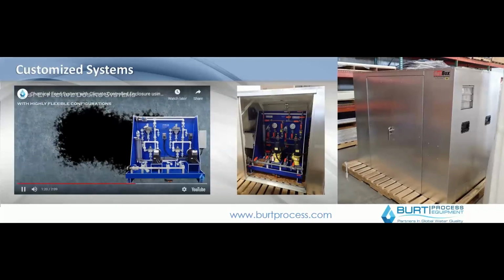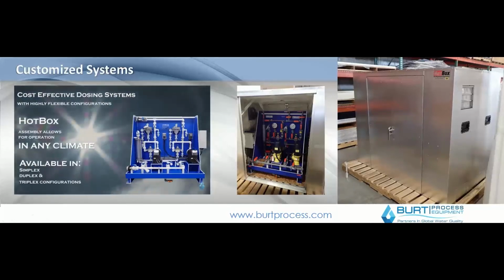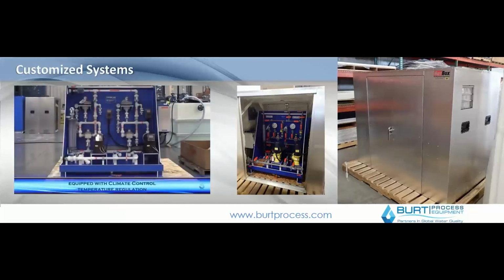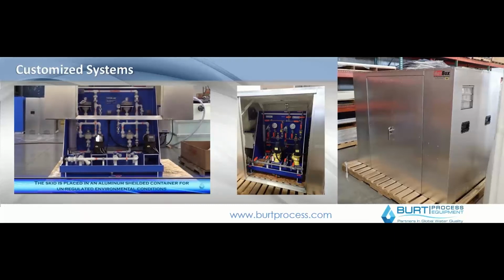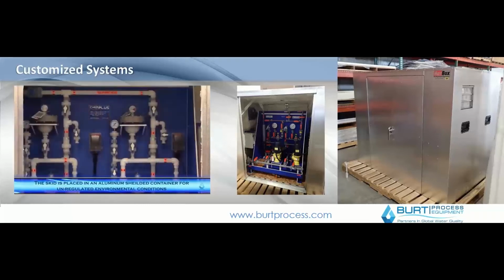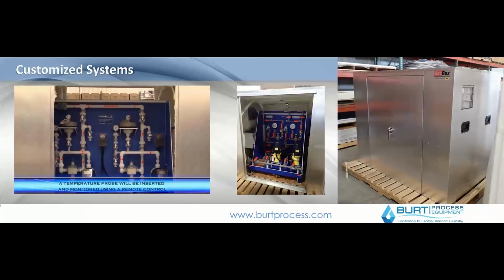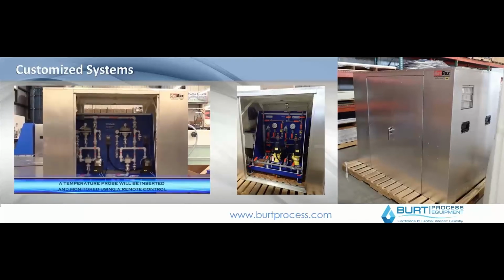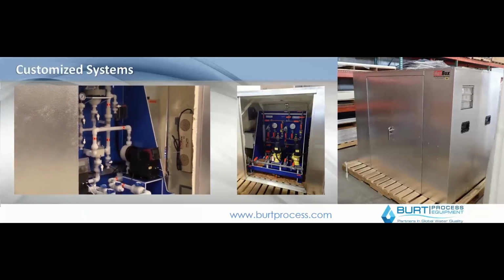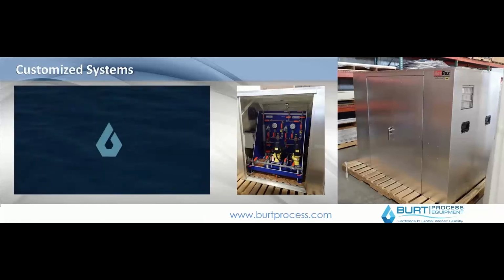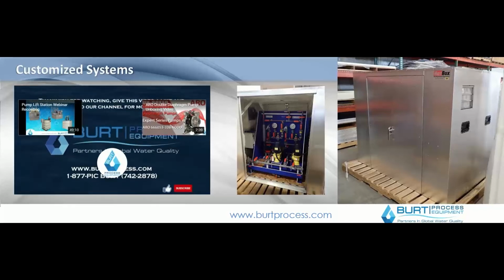Controls can vary quite a bit with these different types of systems, whether it's going to be a full PLC control or more of a junction box design. And these systems were also installed outside. Because of this, they had to be put into more of an environmental based enclosure. And to protect, obviously, thermoplastics, the equipment utilized very much in chemical feed systems, it's chemically resistant, it is not necessarily environmentally resistant. So while heat tracing is an option in some cases, based on the nature of the chemicals involved, as well as the material selections needed because of that, it was very critical to put these in more of an environmental enclosure like you've seen here, and obviously like we've seen through some of our other examples, looking through some of the customized base systems that are utilized in the system.